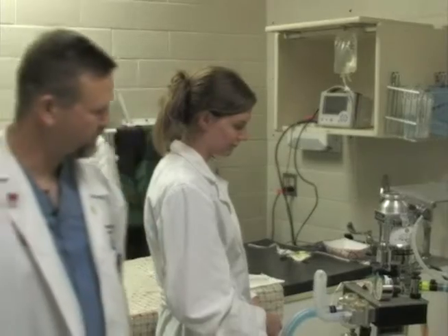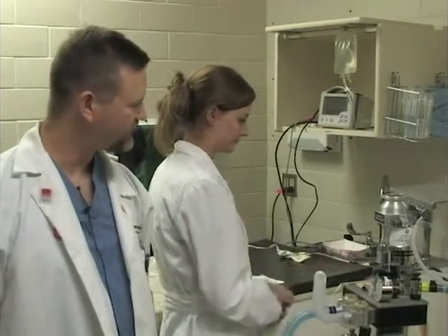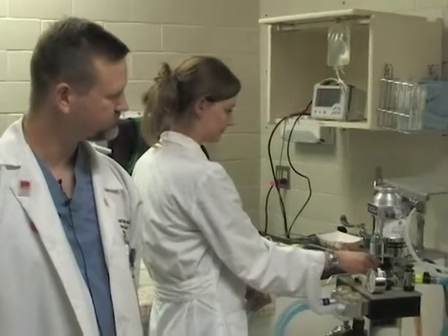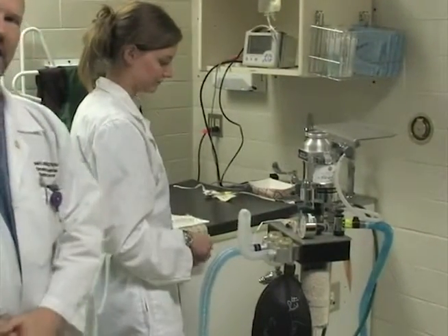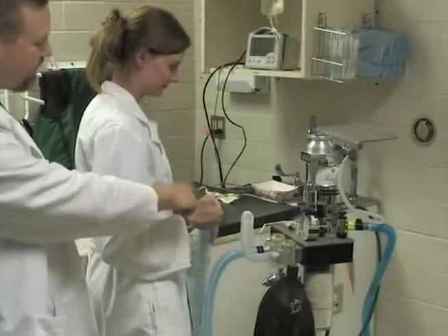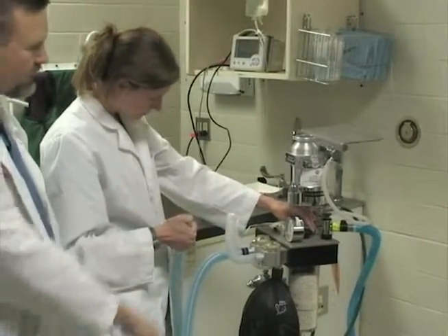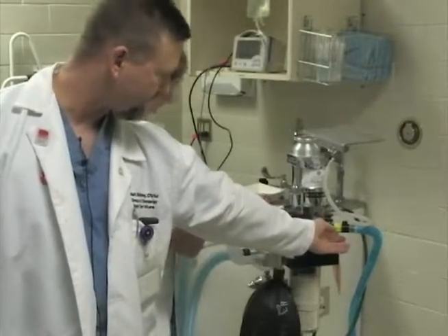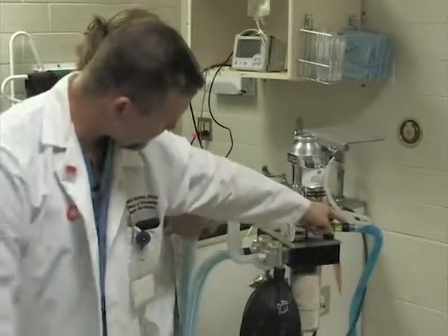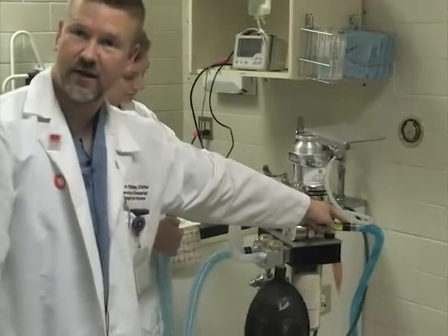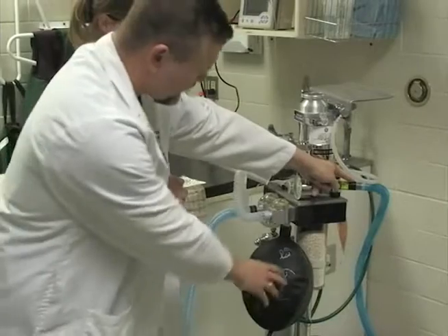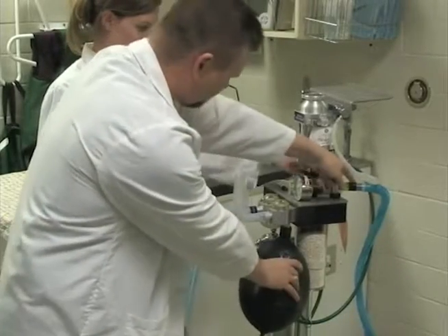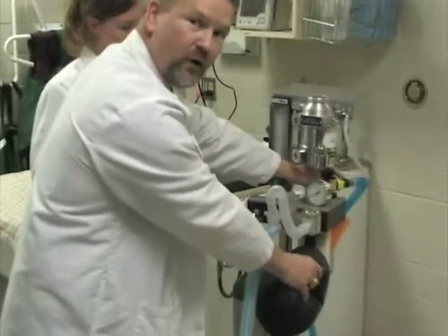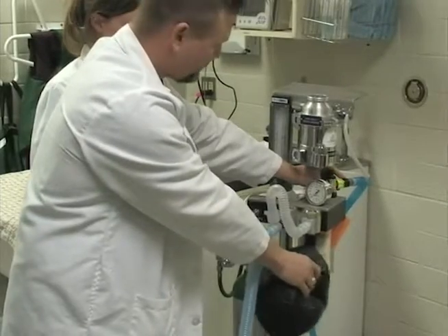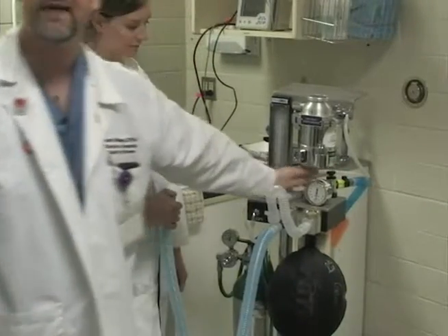All right, so we're going to pressure check this machine. So we turn on the oxygen and the oxygen flow. We plug all of the possible openings from the machine. So we plug the end of the tubing that will connect with our animal, and we close our pop-off valve. And then we make sure that the reservoir bag is filling up with oxygen, with air. And when we place pressure on it, we want to see on the manometer that it can hold at least 30 centimeters of water of pressure without leaking any of that air. So this machine is checked properly. It does not have a leak.